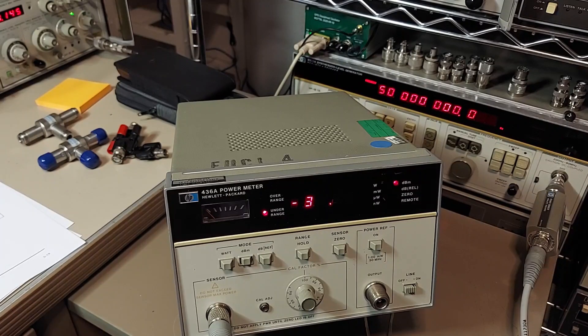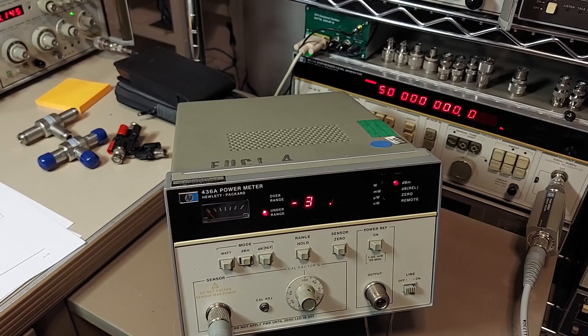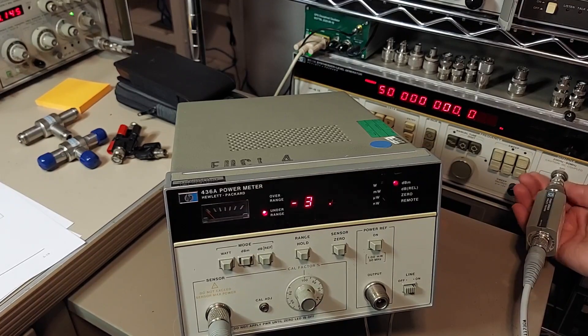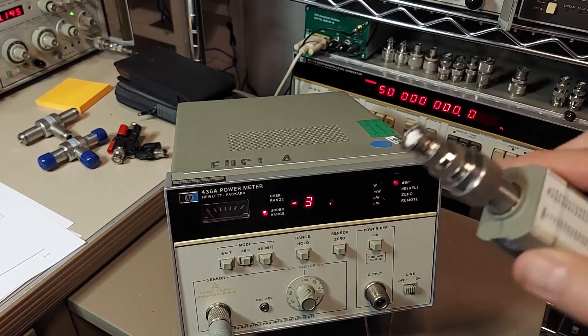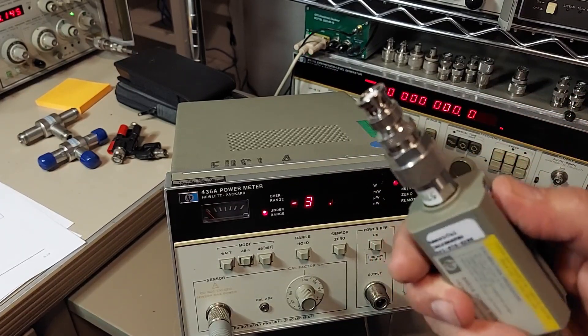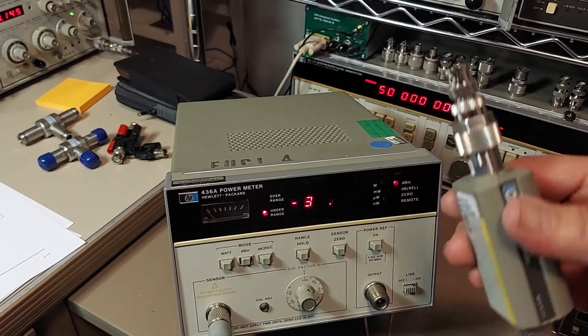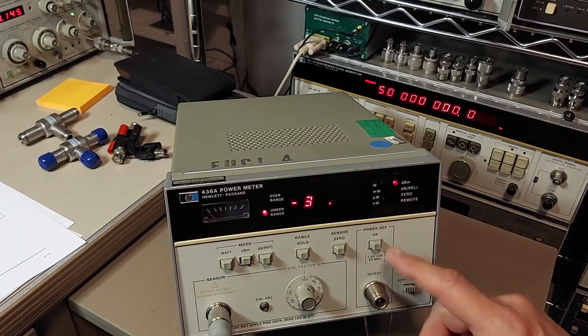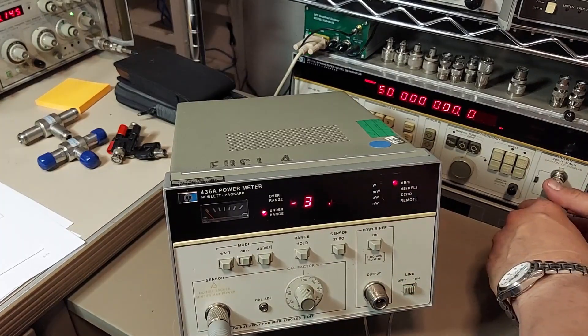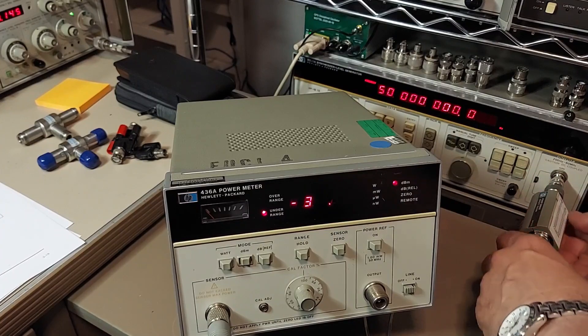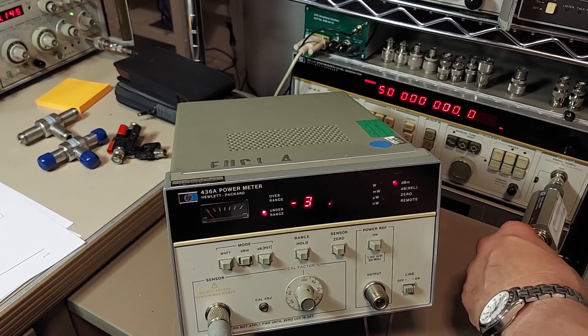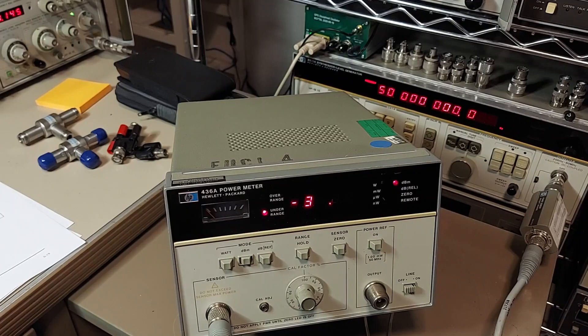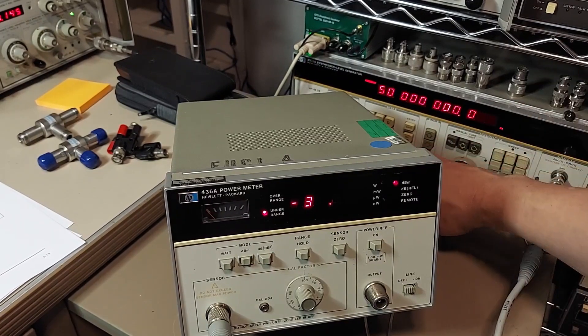All righty, we're all set up ready to go, sensor's plugged in. Although we do have to end up using these N to BNC adapters, so we may get a small amount of loss through that, and depending on how accurate that was, we'll just see how accurate we're gonna get here. So let's start off by switching to amplitude and we'll go to let's start with a minus 25, since that'll be really at the bottom of that sensor.